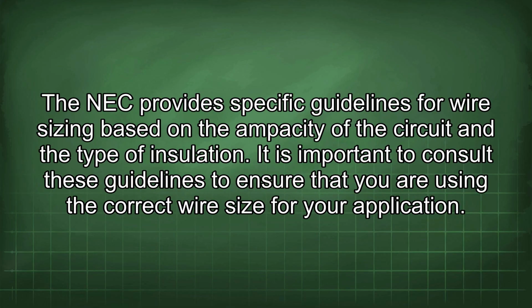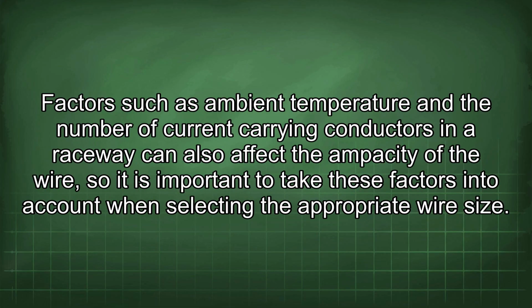The NEC provides specific guidelines for wire sizing based on the ampacity of the circuit and the type of insulation. It is important to consult these guidelines to ensure that you are using the correct wire size for your application. Factors such as ambient temperature and the number of current-carrying conductors in a raceway can also affect the ampacity of the wire, so it is important to take these factors into account when selecting the appropriate wire size.